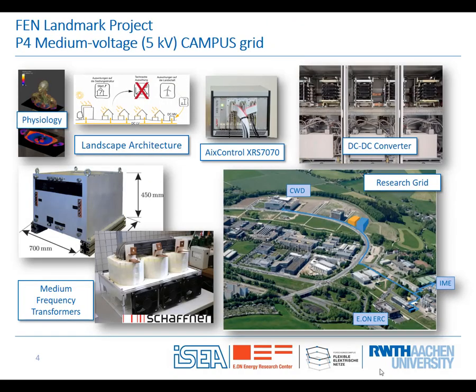So some of the things that we realized so far: this box here is actually a transformer of 2.3 MVA at 1 kilohertz, about 15 times more compact compared to a 50 hertz transformer. At the same time, together with the DC to DC converter, which is 7 megawatt peak but has its highest efficiency at 5 megawatts, we can transmit 7 megawatts of power at efficiencies at rated conditions of more than 99%. So this is as good as a 50 hertz distribution transformer, but consumes far less material.